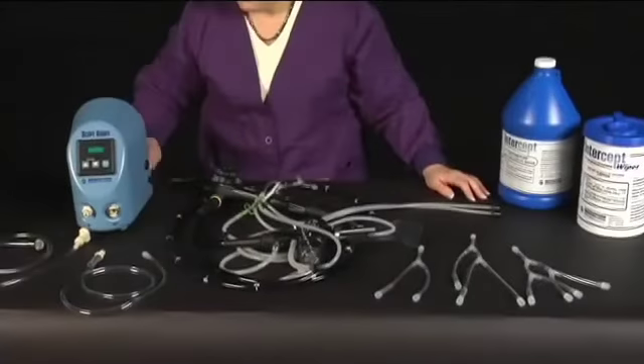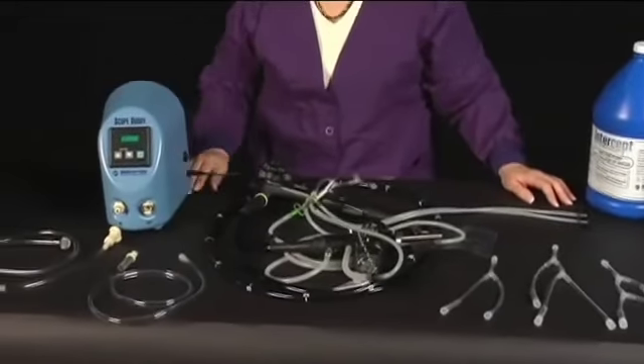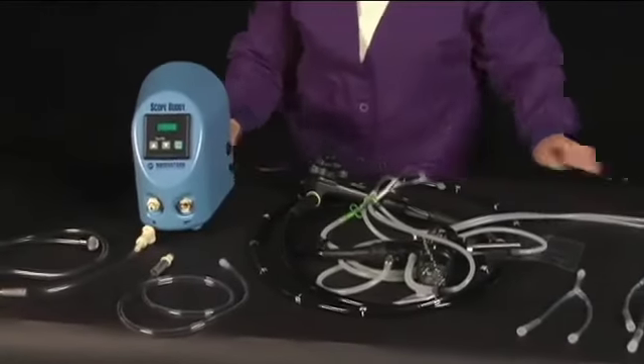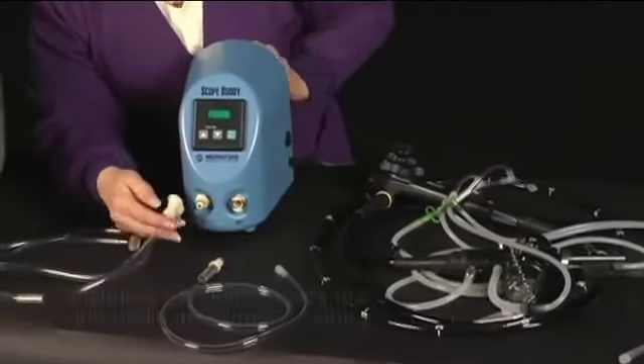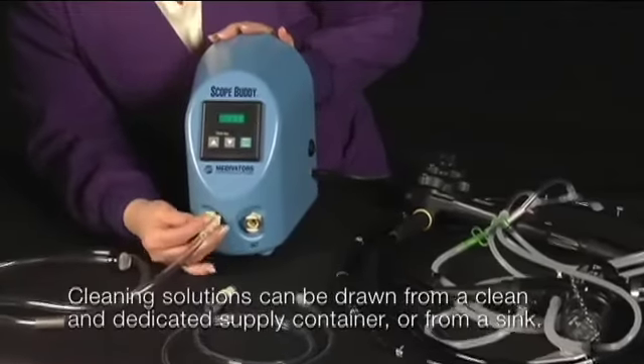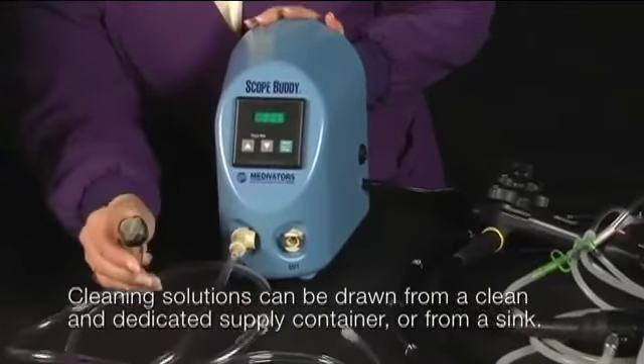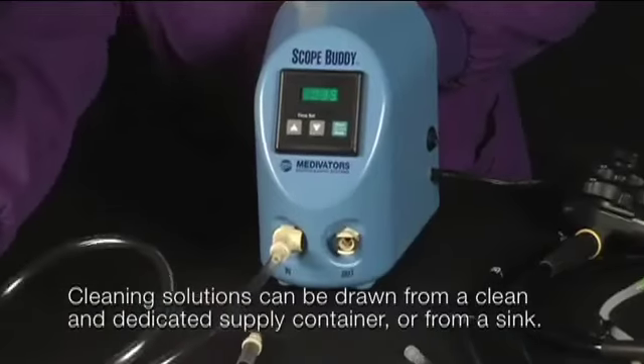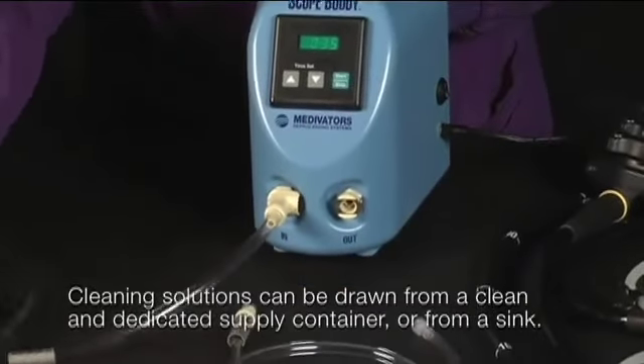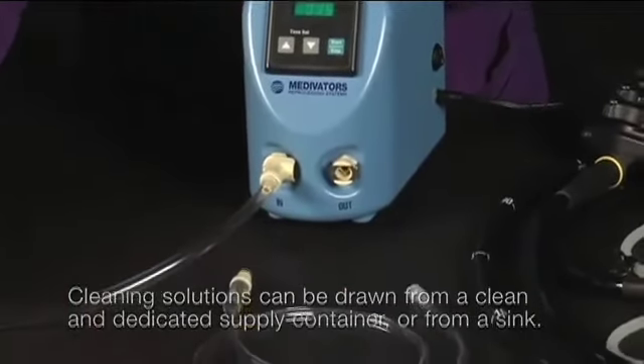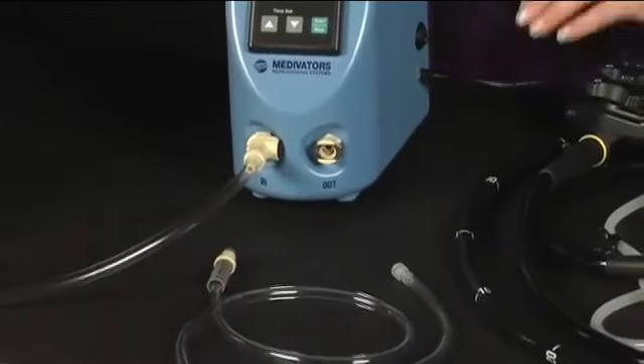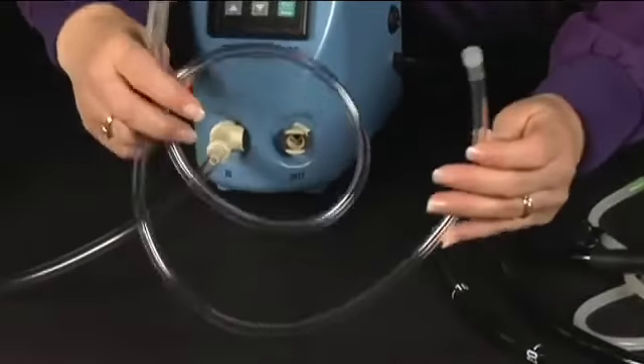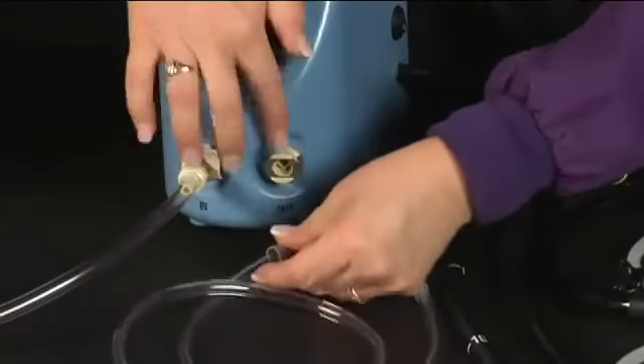Plug the unit in and turn the device on by pressing the power switch. Snap the connector of the fluid intake line to the connection port labeled in and fully submerge the screened end in a sink or clean supply container of detergent solution. Snap the connector of the universal cleaning adapter extension line to the connection port labeled out.